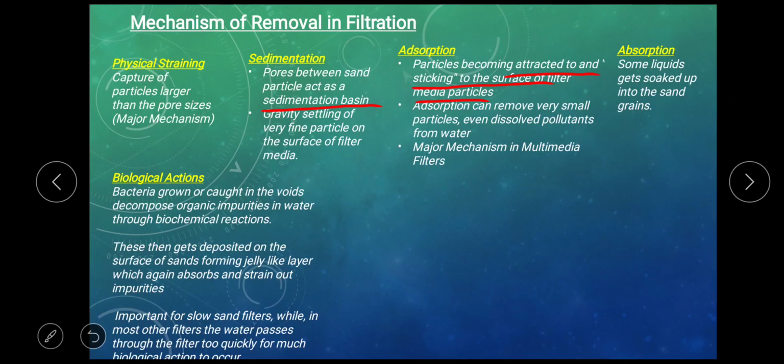With the passage of time, the thickness of the slime layer increases, which helps in further retaining impurities which are even smaller. But with the passage of time, head loss increases and filtration rate decreases. So after a certain interval we have to clean this layer.